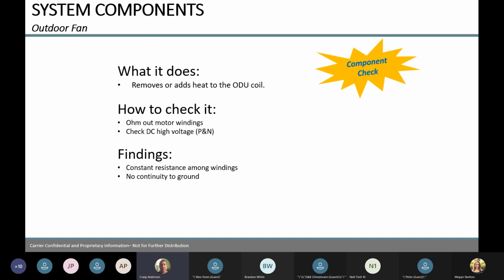So what the outdoor fan does, it takes the heat out of the unit and blows it out. We can ohm out the motor windings, or we can check the DC voltage on the P and N tabs going to that fan motor to see if we have that pulsing voltage going to it.